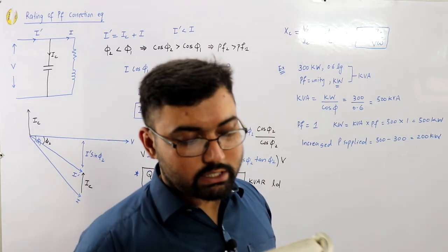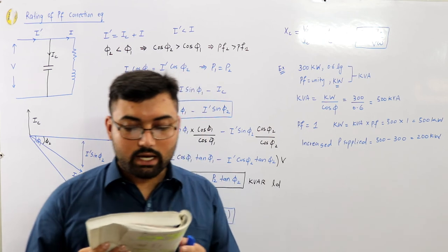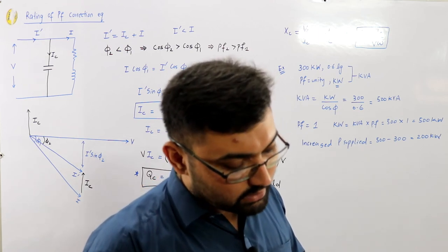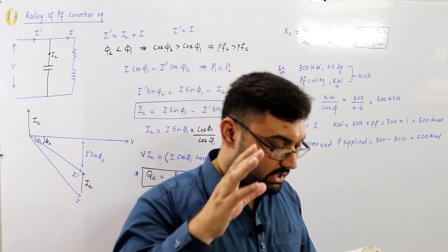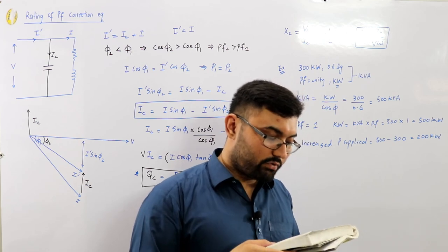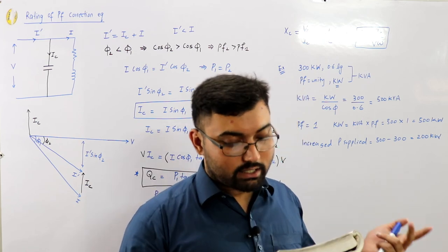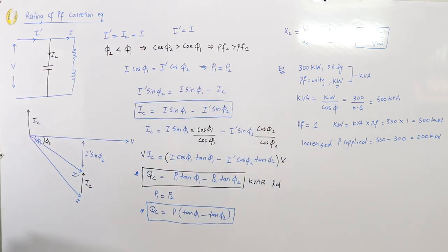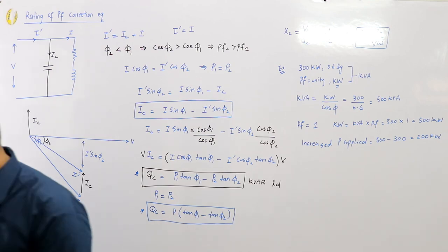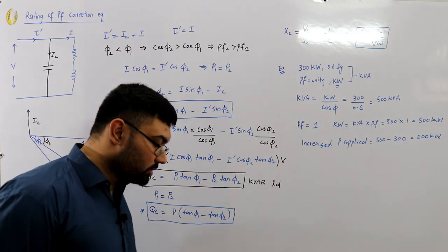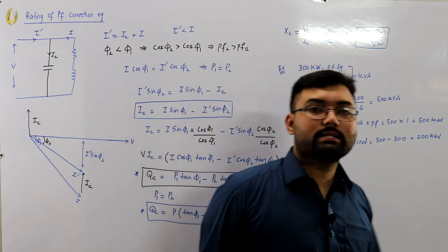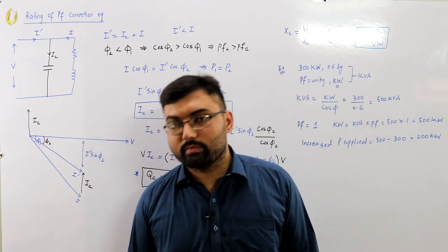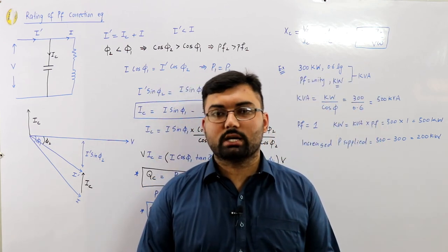This demonstrates the importance of power factor improvement. At unity power factor, 500 KVA equals 500 kilowatts and the engine must develop that full power. At 0.6 power factor, the engine develops only 300 kilowatts though the machine is rated at 500 KVA. We'll discuss more examples in the next video — take care, subscribe to the channel, goodbye.